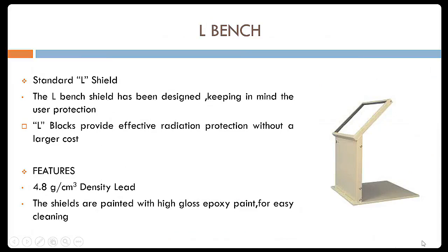The L bench is this kind of L shield. They are designed so that the user will be protected. So we can stand here and do the procedure like this. It is made up of lead with a density of 4.8 gram per centimeter cubed, and it is painted with high gloss epoxy paint so that we can clean it easily.